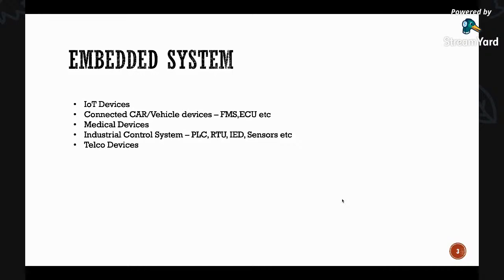So these PLCs talk with a SCADA. And in that case, the embedded device comes in the kind of PLC or rather RTU or any converter, like a protocol converter, which we call a coupler, right? From Modbus to DNP3, or serial to Modbus communications in that case. Again, these embedded devices come in telco devices.